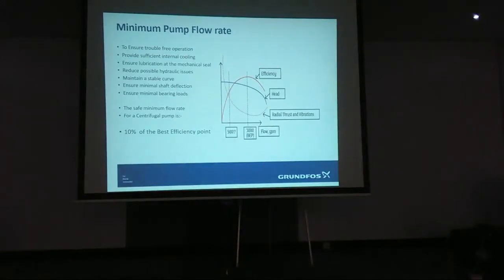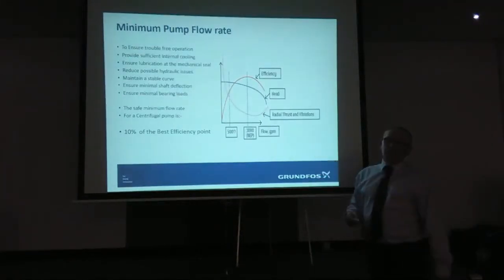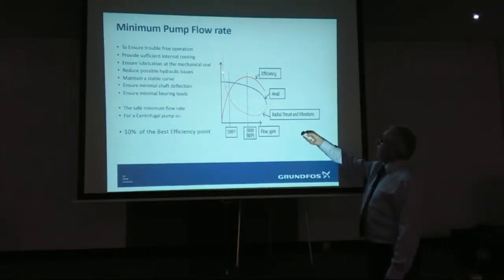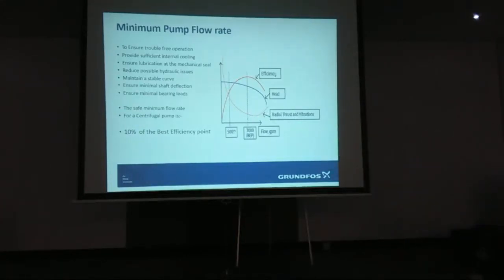The reason being, all centrifugal pumps, mechanically sealed, driven by an electric motor, TEFC, totally enclosed fan cooled motor, have a similar characteristic to this, where there's a curve that nobody produces, and I didn't produce this. And that's radial thrust and vibration loading on centrifugal pumps. And as you can see, as you get to closed valve head, it seems to rise quite high. So as a general rule of thumb, all pump manufacturers state 10% of the best efficiency. As I said earlier on, the best efficiency point is the highest point there, back of those curves. So if we try to select a pump, if that was your duty somewhere there, you've not got a lot of room to play with. If 10 litres a second sits about here somewhere, the best efficiency point might be 8 litres a second, so the minimum flow is 0.8 litres a second.